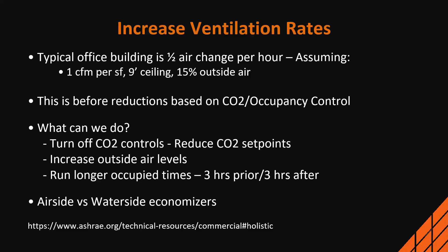So if we take this first step, we start off with our base case example at 15% outdoor air. Say on this particular day it's 80 degrees, and at 80 degrees I can make it to 30% outdoor air at that moment in time. That drops our pass-through rate from 75.6 down to 62.5% pass-through. So now I've captured roughly 37.5% of the virus particles coming through, rather than 25%. So I'm starting to capture a little bit more virus particles.